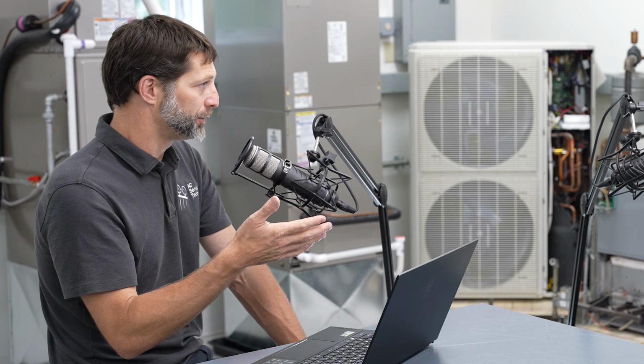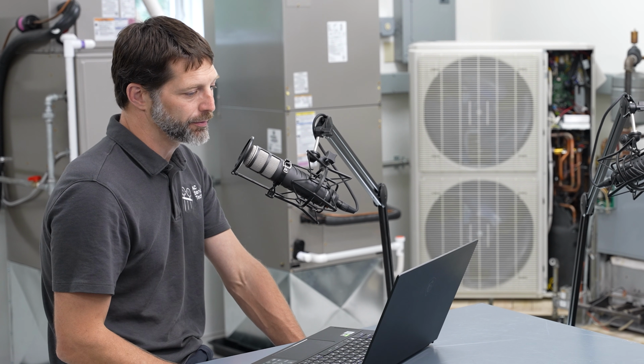No, I agree with you 100%. If it's only happening when the blower motor is turning on, something has to do with pressure. And so there could be a pressure change, and that pressure change may be in the exhaust, or exchanging between the exhaust and the conditioned air, like you said. Could be between the outside environment and the inside environment where the panel is. Just because you think there's no crack or you think it's sealed, you can't rule that out. And a combustion analysis will show you that. So that's an important part.